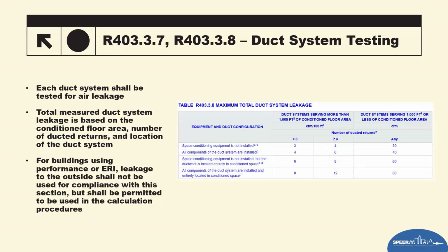For example, if you're looking at one and you say, well, I've got all the components installed, the house is over 1,000 square feet, and I've got more than 3 returns, you've got 6 CFM per 100 square feet, not 4 anymore. If you look to the far right, this came from Energy Star. That's an allowance that says, well, if you've got a small duct system, and let's say your target of 4 CFM or 6 CFM is below 40, then basically you just have to hit 40 or less. You're not going to try to get to that 18 or 23 that I've spent hours fighting in the field, trying to get those things down tight enough. Energy Star says, well, as long as you get to that 40 for that one system, it should be good.